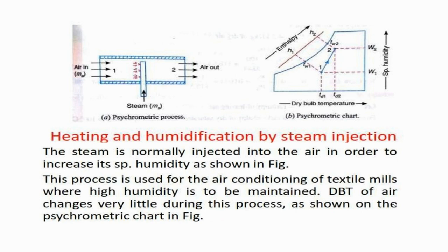This process is achieved by steam injection, where hot steam is injected into the air to increase its specific humidity. This process is used for air conditioning of textile mills where high humidity needs to be maintained and temperature also needs to increase. The dry bulb temperature of air changes very little during this process, as shown on the psychrometric chart where from point one to two, sensible heat added is very less.